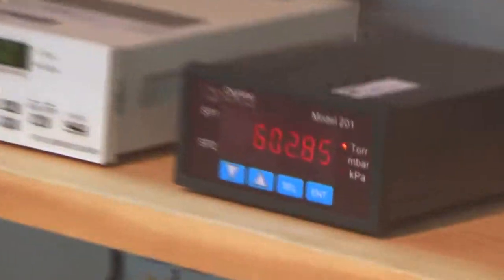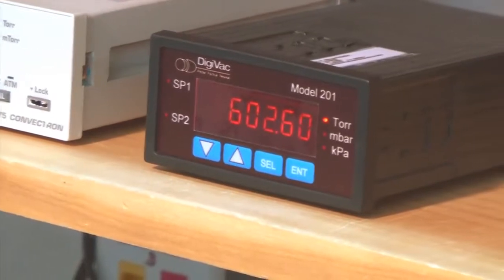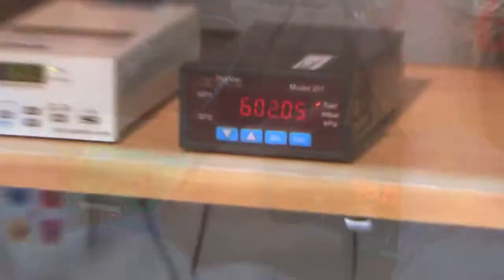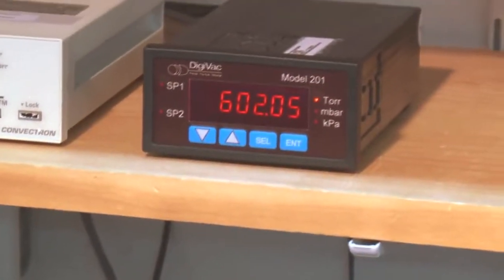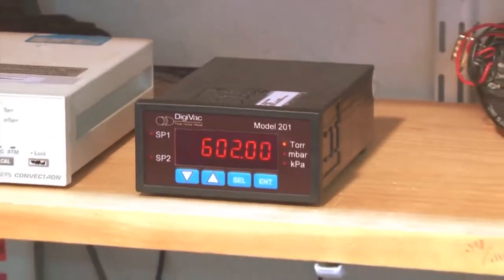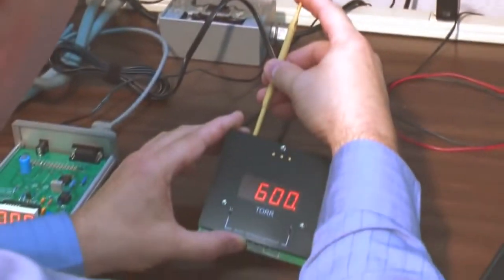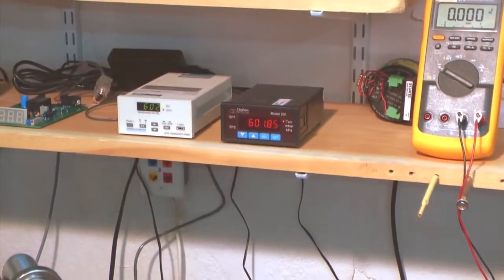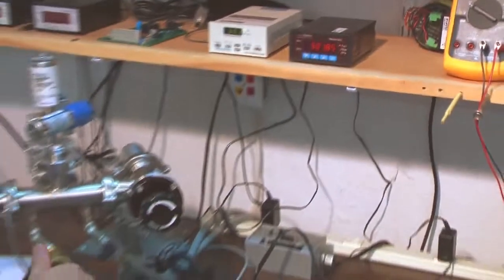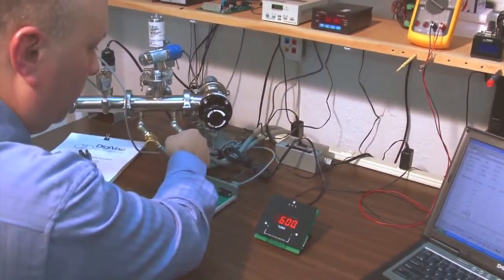As I suspected, our readings have been a little low. We're going to make a secondary correction on our span, using our Baratron indicating 600 torr. Increase our gain by turning the atmospheric potentiometer clockwise so we're right on the threshold of 600 torr. And now we're going to run backwards and take some readings decreasing in vacuum. 600 torr, still 600.